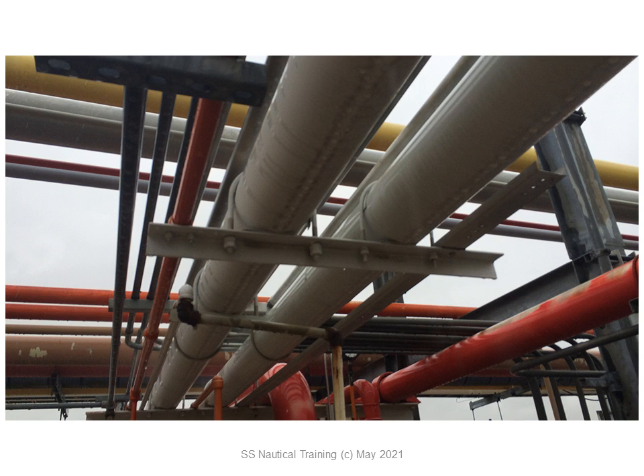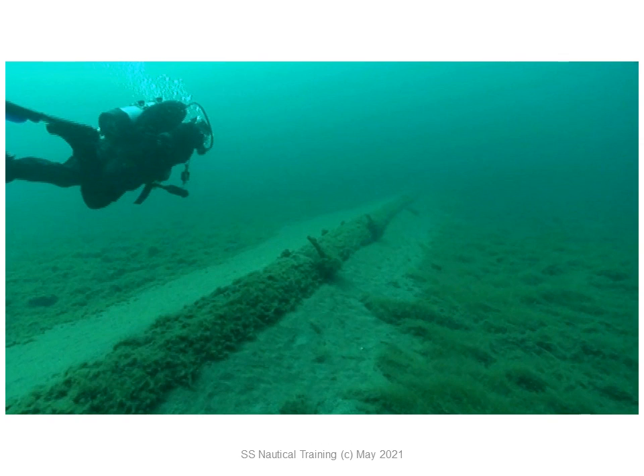Pipelines move, especially during the tank-draining stage of a discharge. The pipelines will almost certainly move if the emergency shutdown system is activated. Regular inspection of the securing and anchor points of the pipeline is required, and any maintenance to adjust the securing arrangements must be completed expeditiously. Any underwater parts of the terminal pipeline must also be inspected.